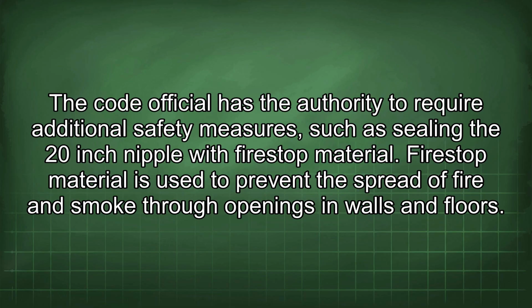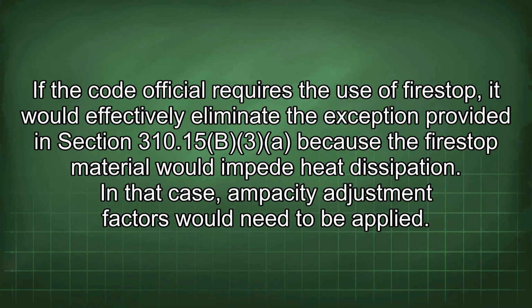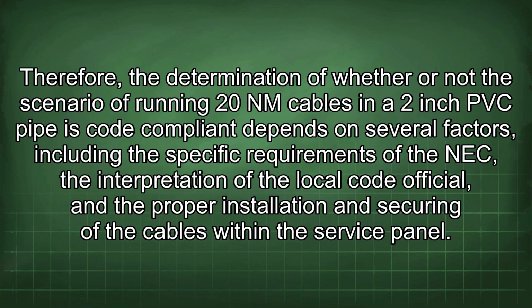Firestop material is used to prevent the spread of fire and smoke through openings in walls and floors. If the code official requires the use of firestop, it would effectively eliminate the exception provided in Section 310.15(B)(3) because the firestop material would impede heat dissipation. In that case, ampacity adjustment factors would need to be applied. Therefore, the determination of whether or not the scenario of running 20 NM cables in a 2-inch PVC pipe is code compliant depends on several factors, including the specific requirements of the NEC, the interpretation of the local code official, and the proper installation and securing of the cables within the service panel.